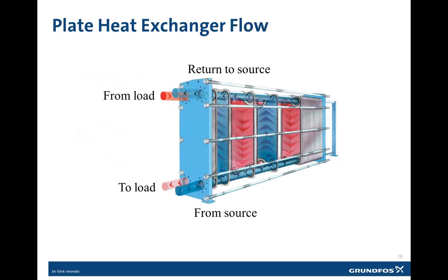This is accomplished through flow patterns between a series of different plates, usually made out of stainless steel, patterned in such a way that the flow is in opposite directions every other plate. So as we can see here, from the load and to the load for heating, or from the load to the source for cooling, and reverse depending on the application. It's patterned so that this flow provides maximum heat transfer from the source to the load. So it's essentially known as a counterflow.